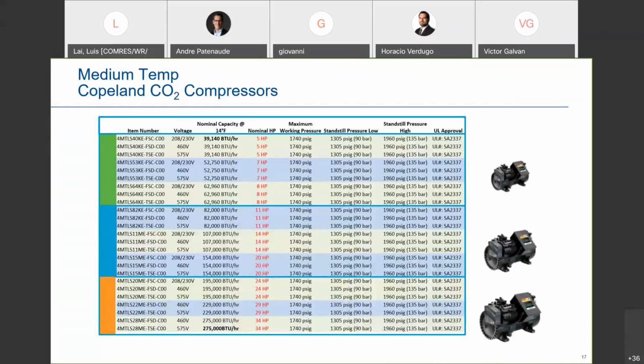And we've actually released these products in 3 groupings. The middle grouping were the first ones released, called the P1, but it doesn't really matter at this point. But they were the first groupings of compressors to be released. 82,000 BTU, 107,000, and 154,000. That's at a plus 14 saturated suction, which follows the European rates when you convert to Celsius. So 11, 14 to 20 horsepower.